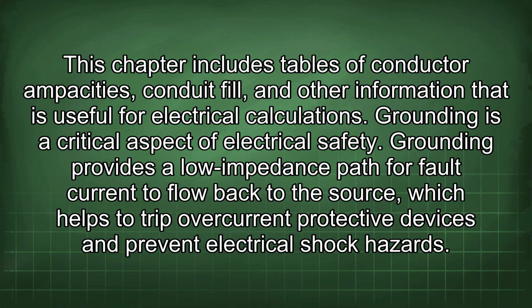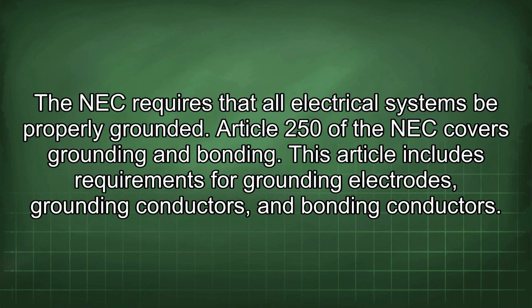Grounding is a critical aspect of electrical safety. Grounding provides a low impedance path for fault current to flow back to the source, which helps to trip overcurrent protective devices and prevent electrical shock hazard. The NEC requires that all electrical systems be properly grounded. Article 250 of the NEC covers grounding and bonding. This article includes requirements for grounding electrodes, grounding conductors, and bonding conductors.